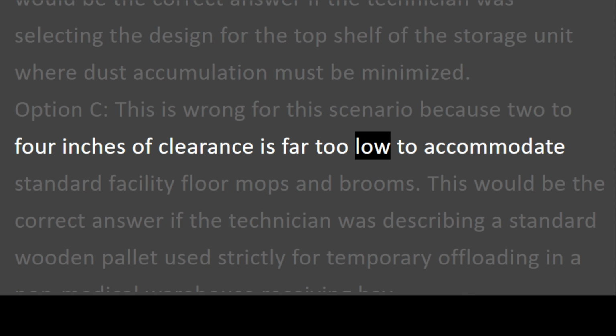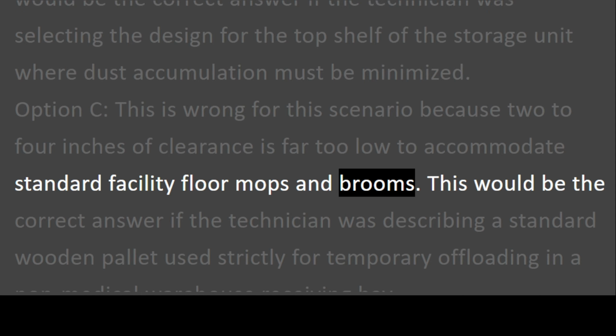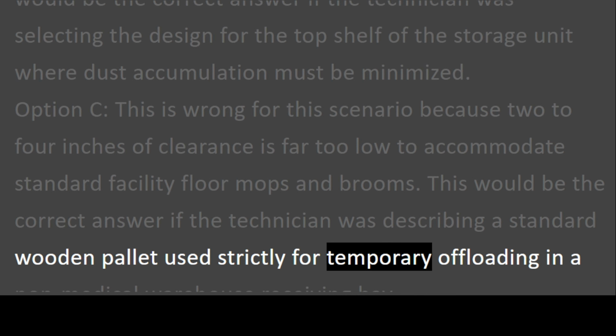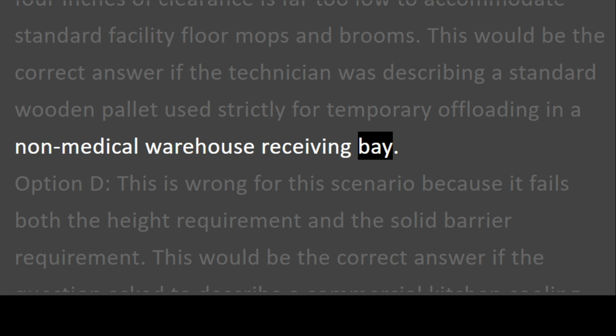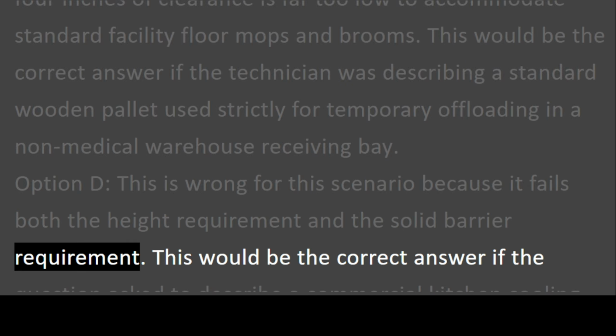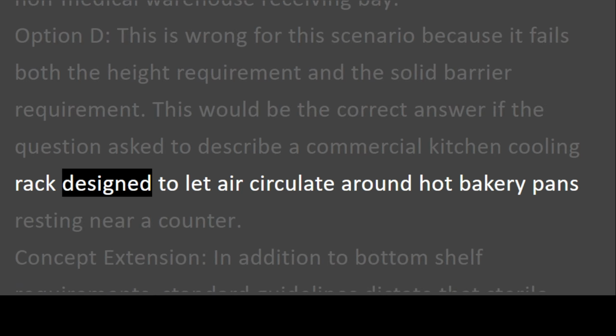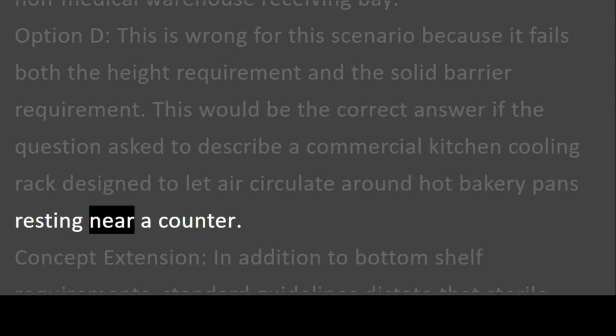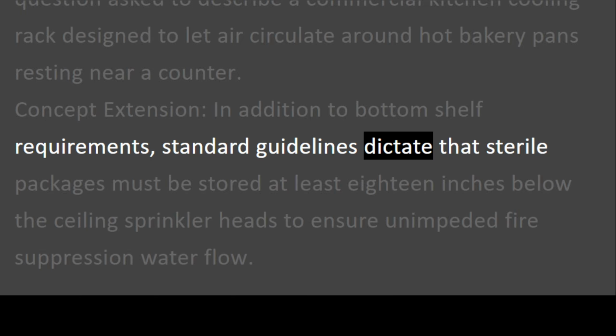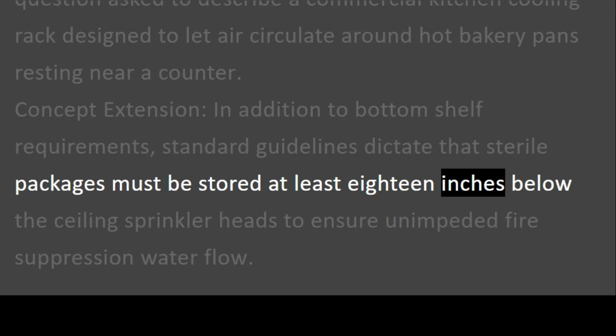Option C. This is wrong for this scenario because 2 to 4 inches of clearance is far too low to accommodate standard facility floor mops and brooms. This would be the correct answer if the technician was describing a standard wooden pallet used strictly for temporary offloading in a non-medical warehouse receiving bay. Option D. This is wrong for this scenario because it fails both the height requirement and the solid barrier requirement. This would be the correct answer if the question asked to describe a commercial kitchen cooling rack designed to let air circulate around hot bakery pans resting near a counter. Concept extension. In addition to bottom shelf requirements, standard guidelines dictate that sterile packages must be stored at least 18 inches below the ceiling sprinkler heads to ensure unimpeded fire suppression water flow.